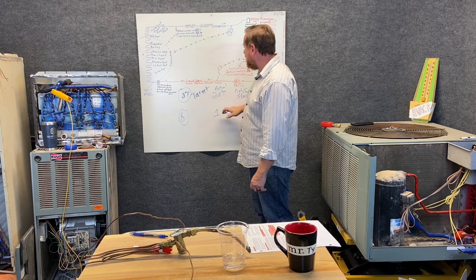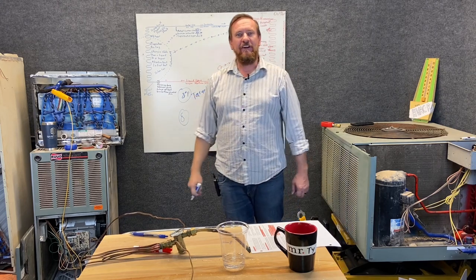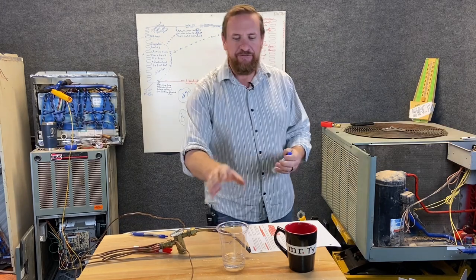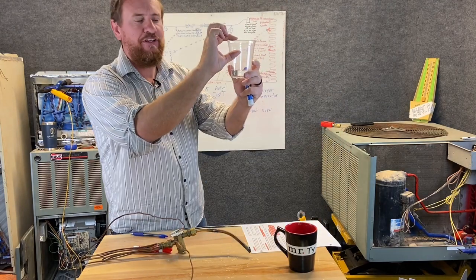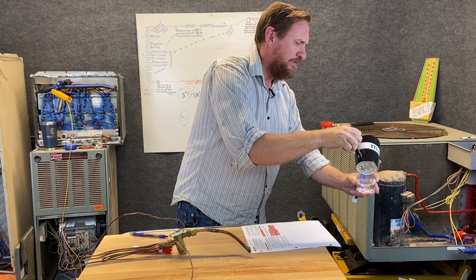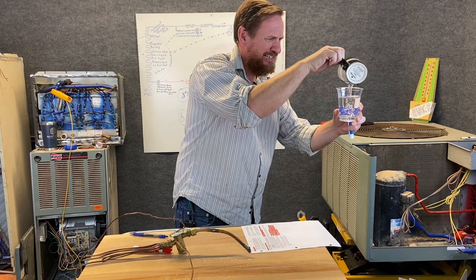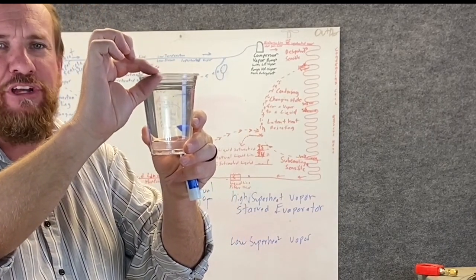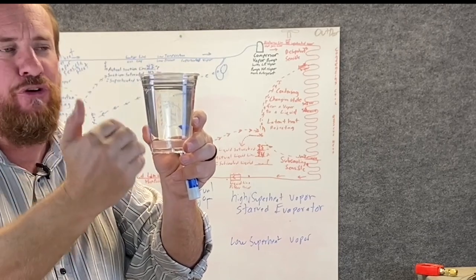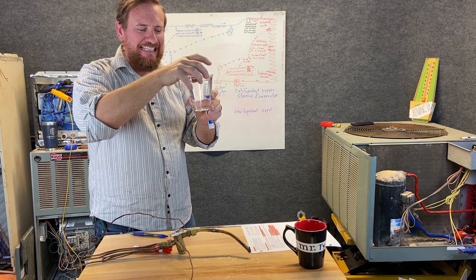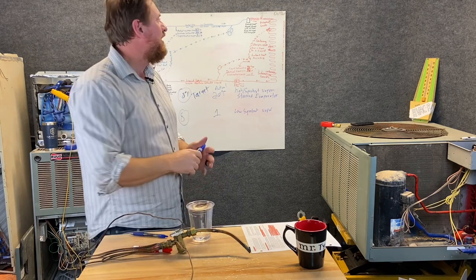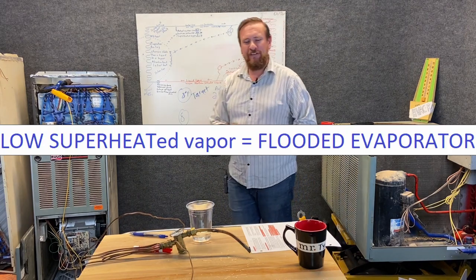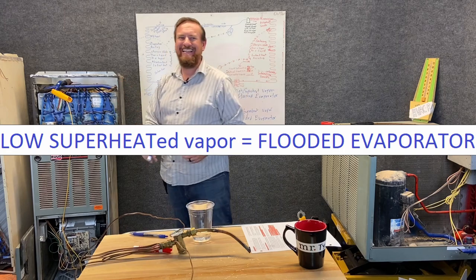That's a huge issue, but we're also very low. We're under the superheat target. We're too low. So we have low amount of superheated vapor. So this is going to be called low superheat vapor. So if we think about our superheat vapor, we want eight degrees of superheated vapor. But I only have one degree of superheated vapor. That means I've flooded. I've overfilled my evaporator. I'm about to overflow and get liquid into my compressor. We don't want liquid in our vapor pump. So that's going to be a huge issue. So low superheated vapor means a flooded evaporator. Too much refrigerant inside of that evaporator.